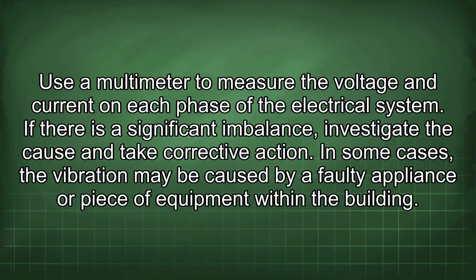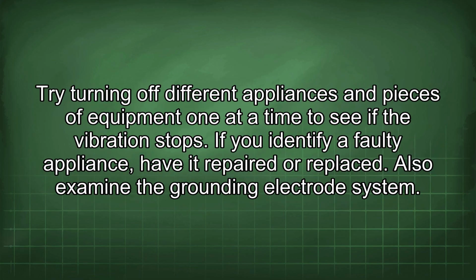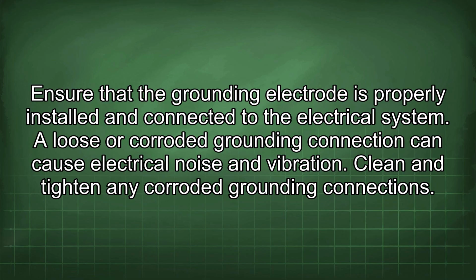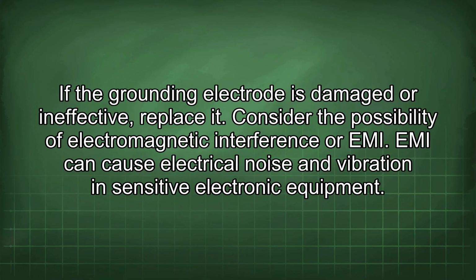In some cases, the vibration may be caused by a faulty appliance or piece of equipment within the building. Try turning off different appliances and pieces of equipment one at a time to see if the vibration stops. If you identify a faulty appliance, have it repaired or replaced. Also examine the grounding electrode system. Ensure that the grounding electrode is properly installed and connected to the electrical system. A loose or corroded grounding connection can cause electrical noise and vibration. Clean and tighten any corroded grounding connections. If the grounding electrode is damaged or ineffective, replace it.